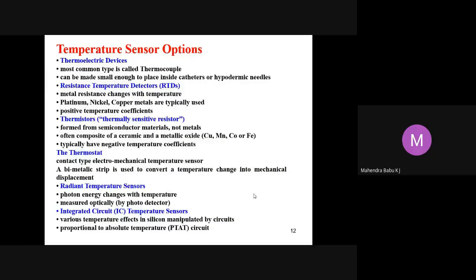They have positive temperature coefficients. Thermistors are also known as thermally sensitive resistors, formed from semiconductor materials, not metals, often composites of ceramics and metallic oxides like copper, manganese, cobalt, or iron. They typically have a negative temperature coefficient. Thermostats are contact-type electromechanical temperature sensors, where a bimetallic strip is used to convert the temperature change into a mechanical displacement.